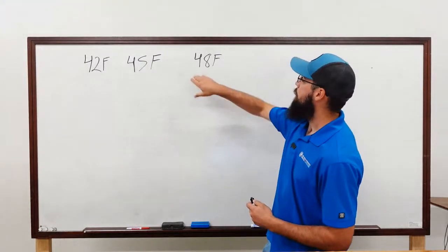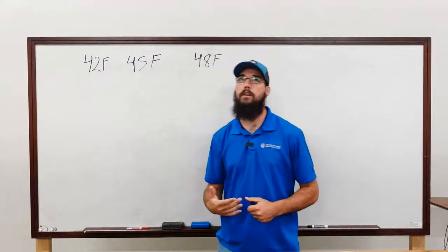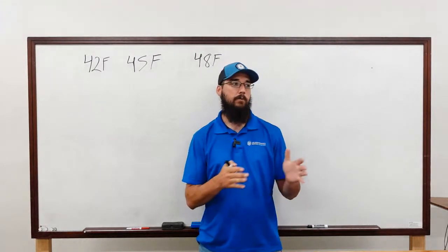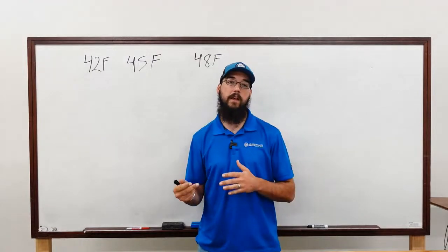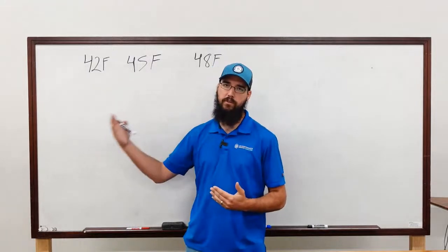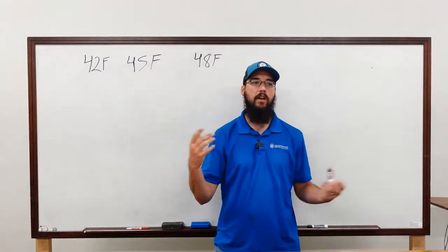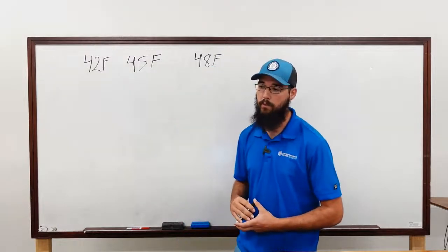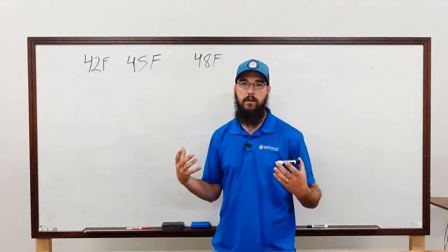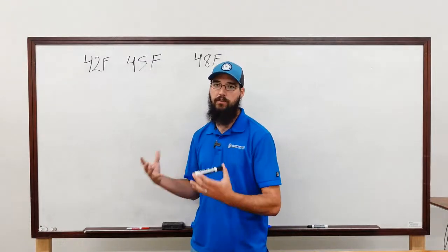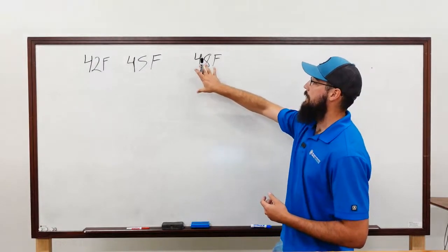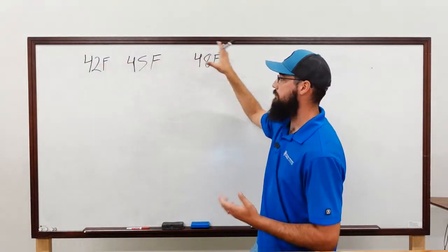But anyway, 48 is pretty typical for a building that's maybe going into a lighter load. We've got some buildings right now that have a fairly light load in the mornings and even during some of the days. This week in particular, we've had a hotter week, so they're pushing their set points back down. But there are buildings that consistently run a 48 degree set point. If you're not having humidity issues and you're mostly just worried about processing the load on the sensible side, that's not really that big a deal. You can run 48 just fine. And this is during a normal cooling summer.